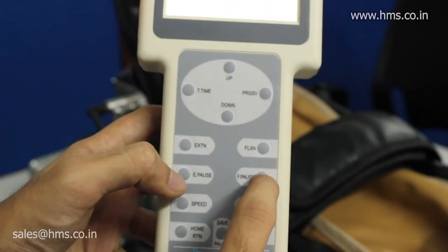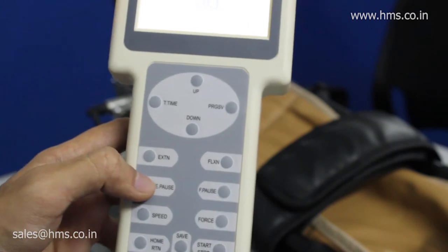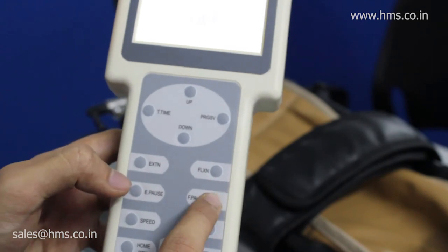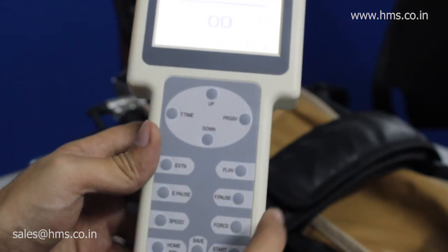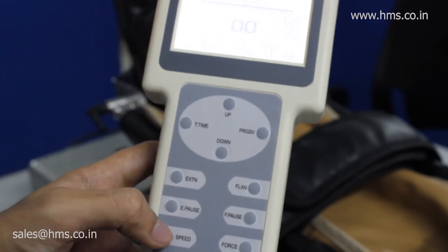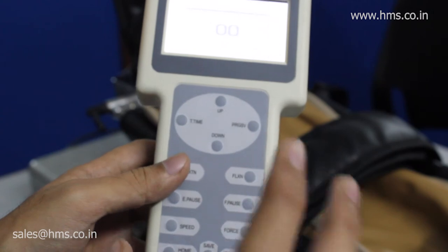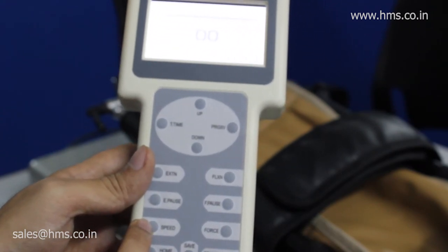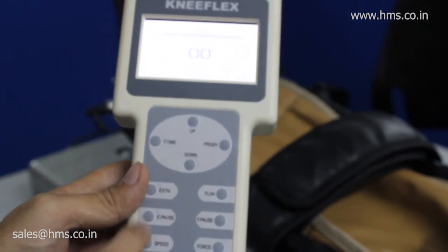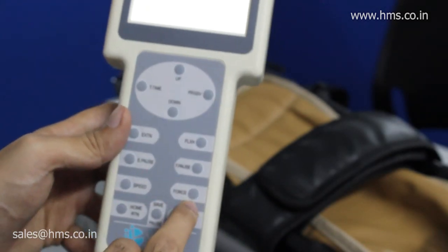Next to the extension and flexing angle buttons are the extension pause and flexing pause. The patient can pause at a certain degree — at their limit — using these extension and flexing pause settings. For speed, the lowest speed is 55 degrees per minute and the top speed is 110 degrees per minute. The speed ranges from level 1 to 10, where level 1 is 55 degrees per minute and level 10 is 110 degrees per minute.